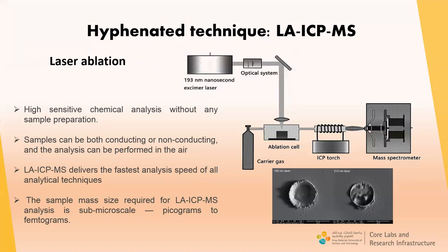Laser ablation is the process of generating fine particles from a sample surface by focusing a laser beam. The ablated particles are then transported into the plasma of the ICP-MS instrument. The main advantages of this method are the possibility of highly sensitive chemical analysis without any sample preparation; samples can be both conducting and non-conducting; and the analysis can be performed in air. LA-ICP-MS delivers the fastest analysis speed of all analytical techniques, and the sample mass required is at the sub-microscale — picograms to femtograms.